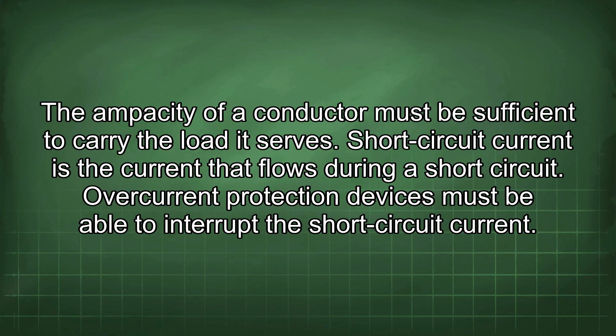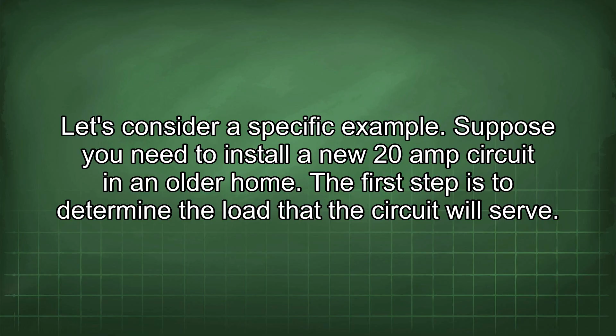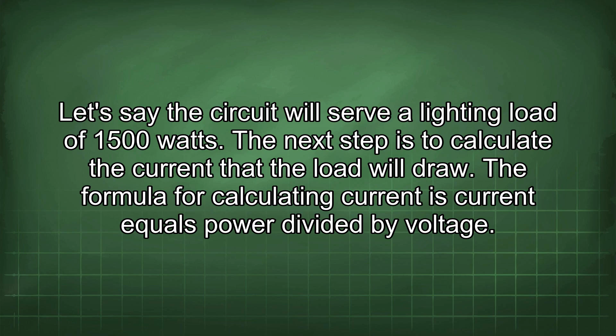Let's consider a specific example. Suppose you need to install a new 20 amp circuit in an older home. The first step is to determine the load that the circuit will serve. Let's say the circuit will serve a lighting load of 1500 watts. The next step is to calculate the current that the load will draw. The formula for calculating current is current equals power divided by voltage. In this case, the current equals 1500 watts divided by 120 volts, which equals 12.5 amps.